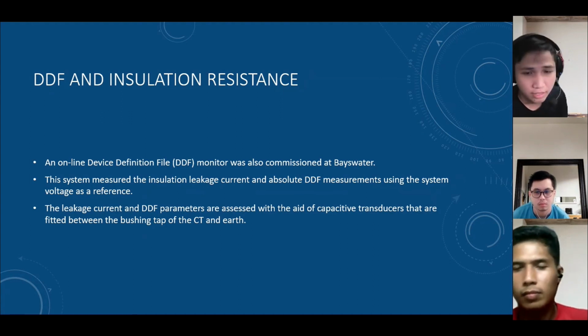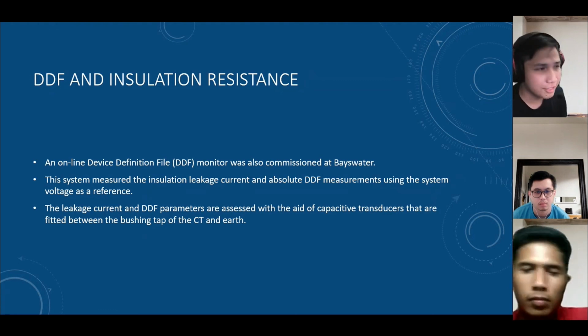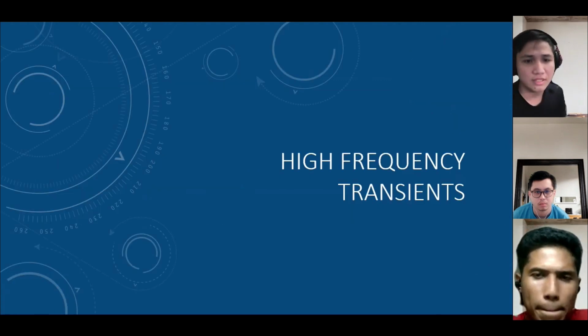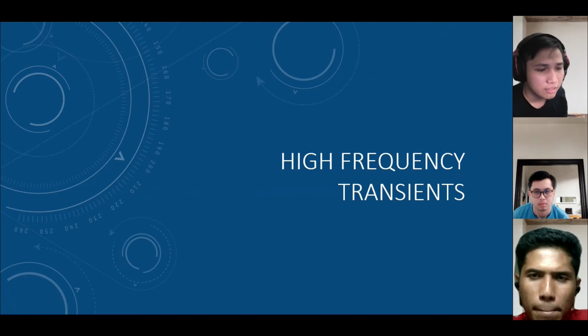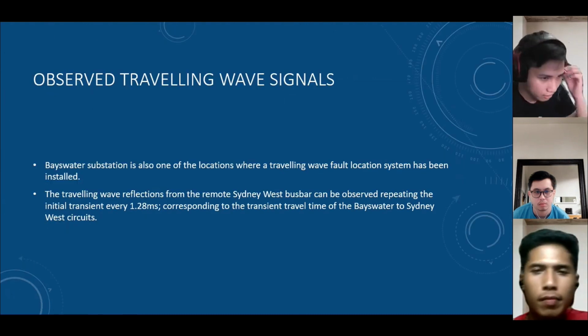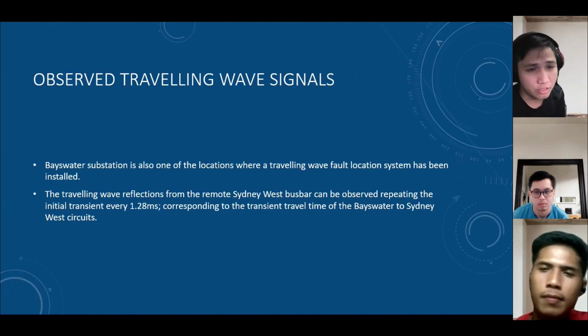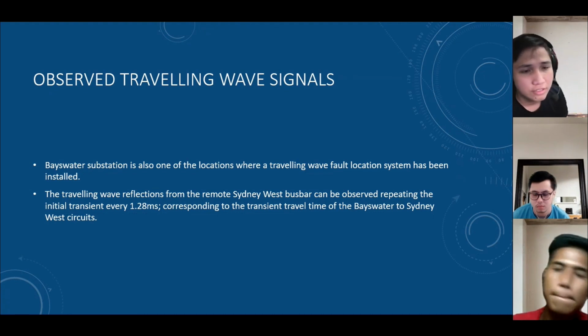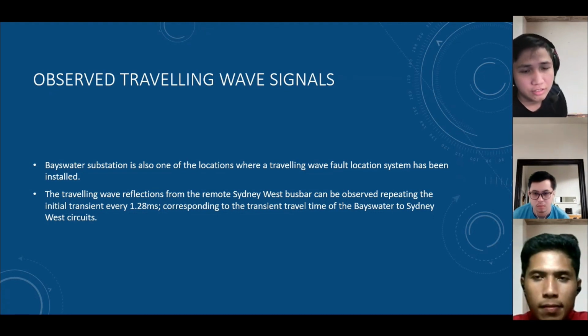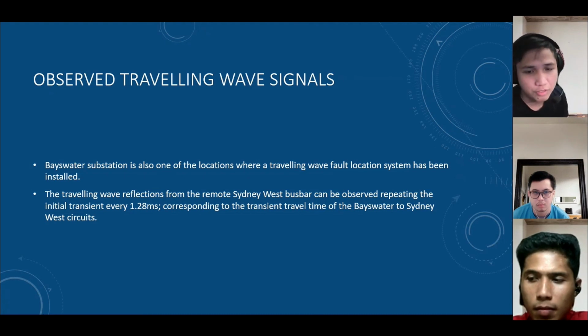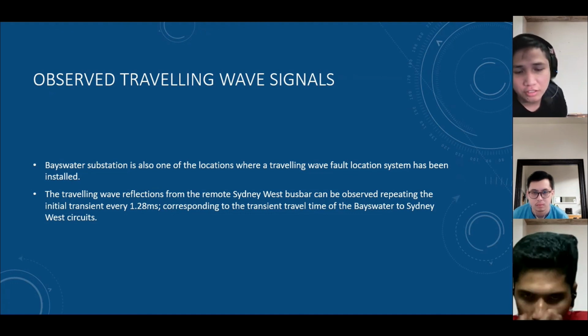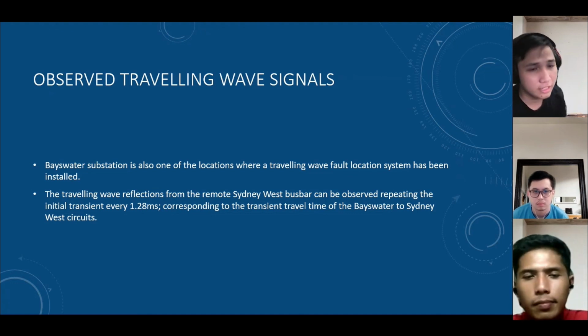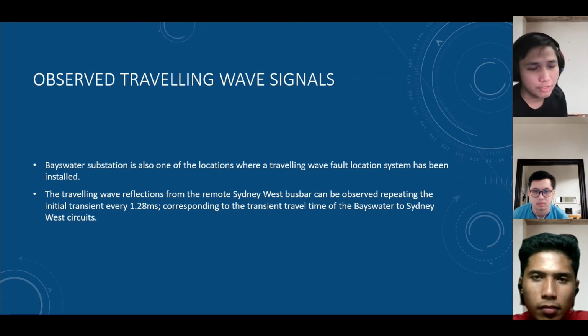So the third method is high frequency transient. Next slide. There are two techniques used on this one. The first is observing the traveling wave signal. The traveling wave signal is recorded remotely at Sydney West Bus Bar, where the initial transient can be observed repeating every 1.28 milliseconds, corresponding to the transient travel time of the Bayswater to Sydney West circuit. So this one is basically about the wave signal.